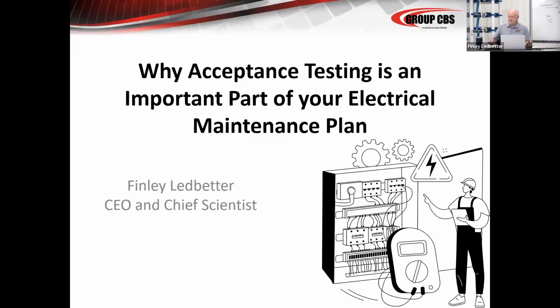Let's talk about what acceptance testing is. We're going to talk about MTS or maintenance testing in a subsequent session. Today, we're going to target acceptance testing and what it does and how it comes to play in the overall plan. So ATS is one major building block in your overall reliability plan, and reliability is what it's all about. But the plant has to rely on this equipment to be an isolation device, a distribution device, and to be an overcurrent or some power parameter protective device.